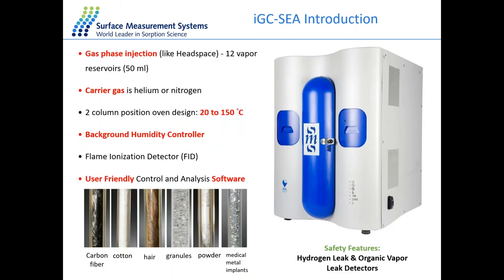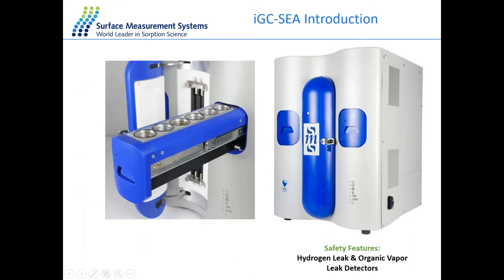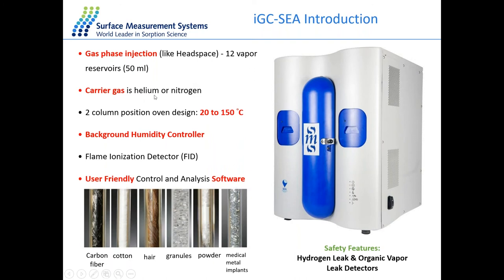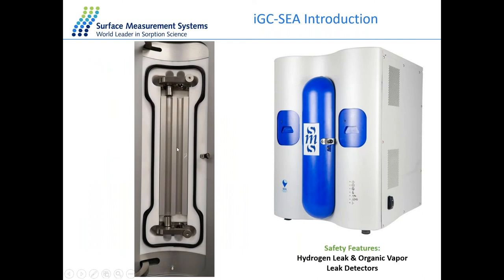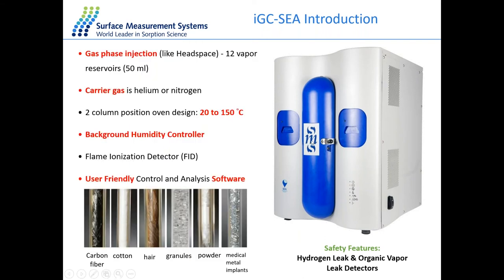The basic IGC procedure: pack the column with the sample of interest, select different probes for different interactions — non-polar probes for dispersive surface energy, polar probes for specific interactions — and inject probe molecules at different concentrations. From the detected signal, calculate the surface properties of the solid inside the column. The IGC instrument injects all solvents directly from the gas phase. It can hold 12 solvents simultaneously — six on each side — with helium or nitrogen as the carrier gas. The column oven ranges from 20 to 150°C, there are two sample positions running in sequence, and the detector is an FID, very sensitive for organic vapors, with automatic hydrogen or organic vapor leak detection for safety.